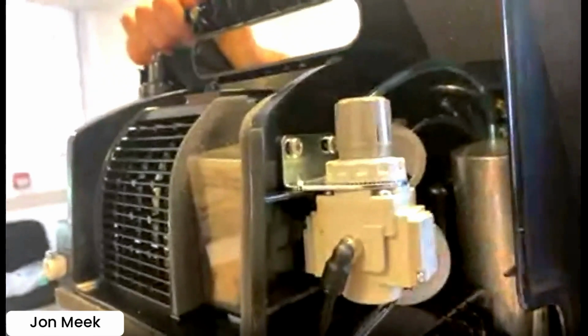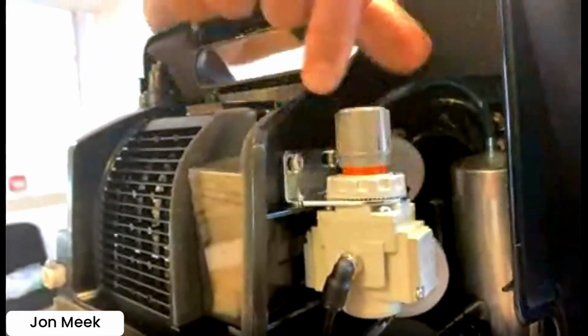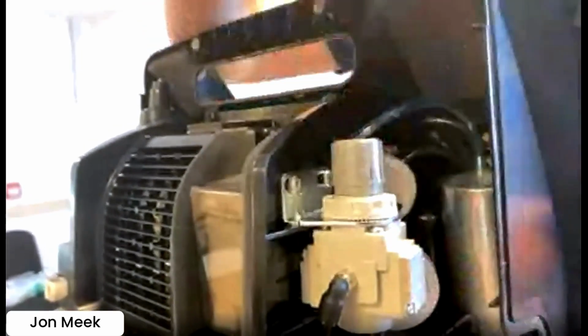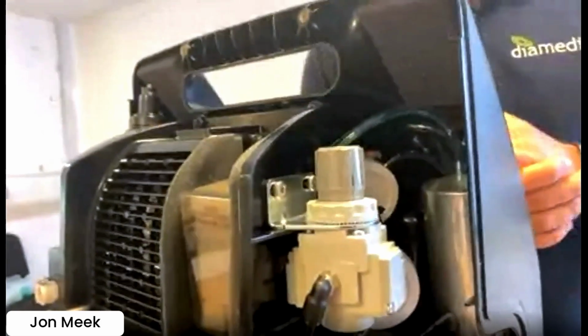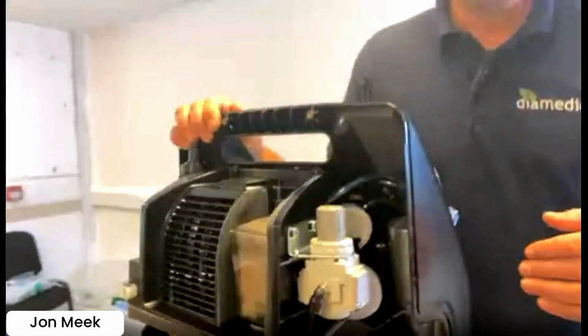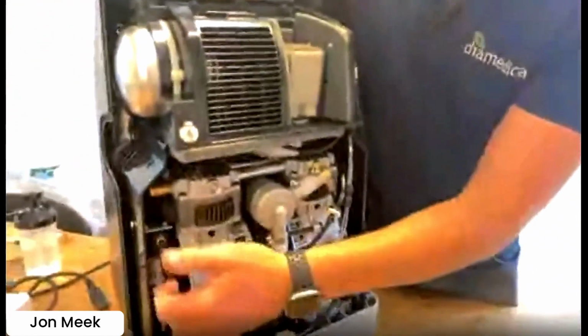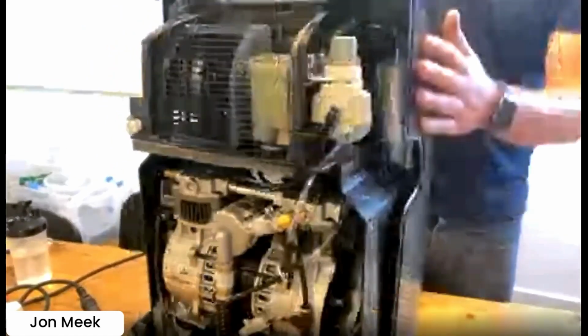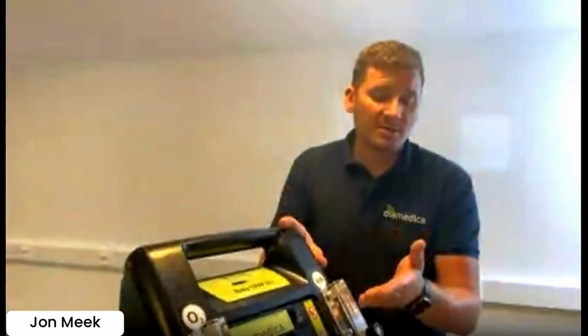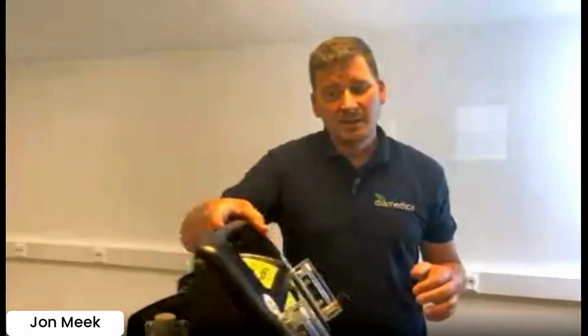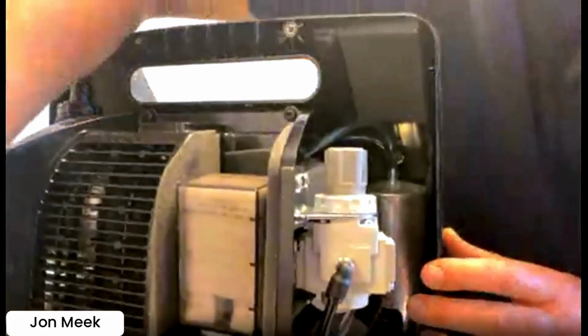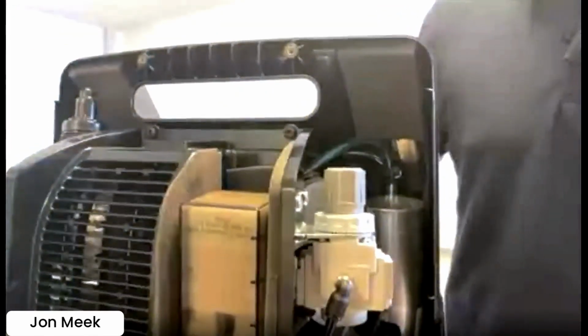Coming from the water trap, so we've removed the moisture, we come up over the top to a pressure regulator. So this is what's maintaining the safe pressure, but also maintaining a steady flow. This is just set in the factory. The outlet pressure is set to 0.55 of a bar. If you set it too high, the moisture will not have time to be removed from the water trap, and it will also fluctuate on the airflow meter. So we want it to be a steady flow output. So this regulator needs to be set to 0.55 of a bar, which will mean you get no moisture coming from the flow meter, and also you get a steady flow on the flow meter.